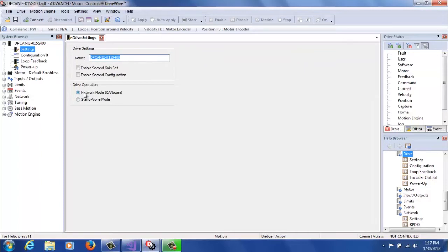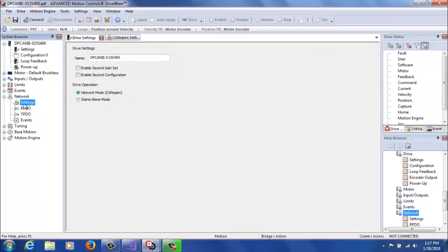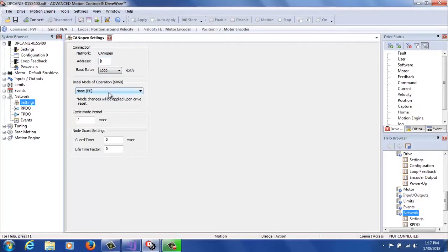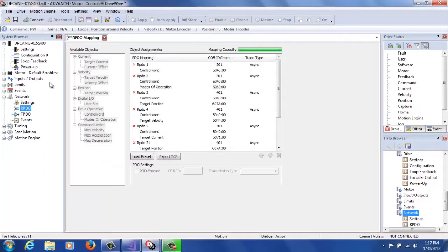You're going to go to network settings. You're going to want to set the address so that it's unique on the CAN bus. You'll want to make sure the baud rate matches whatever the baud rate is on the bus, and finally set the initial mode of operation to either none or configuration zero.